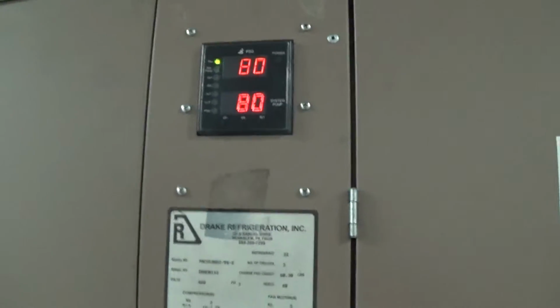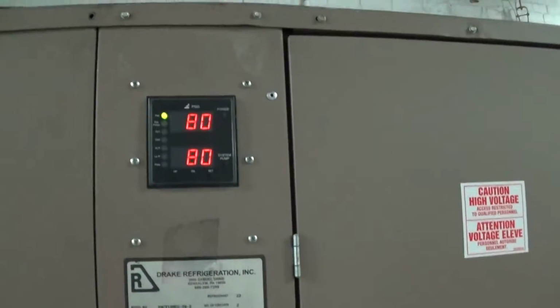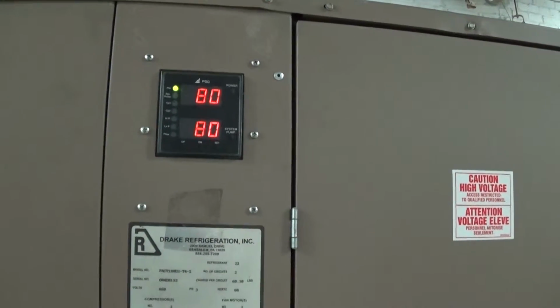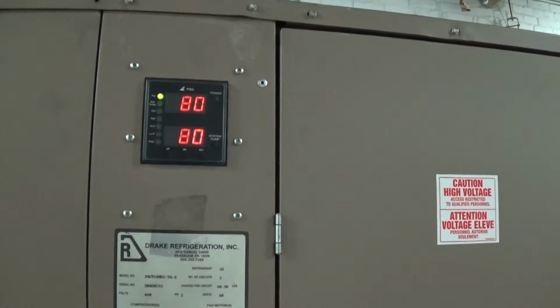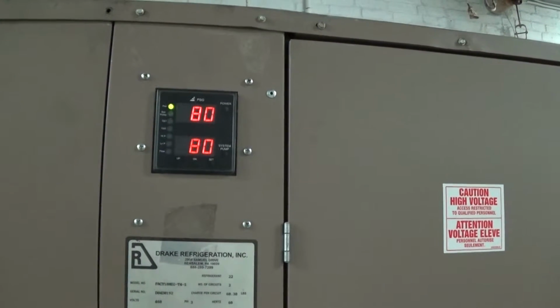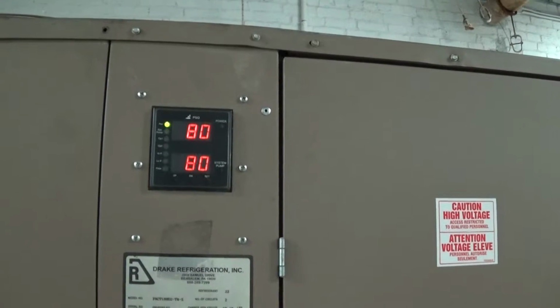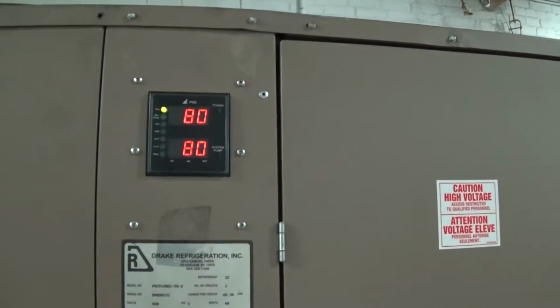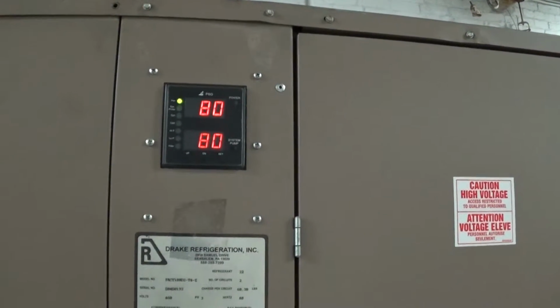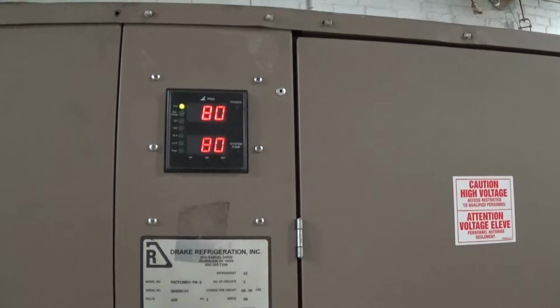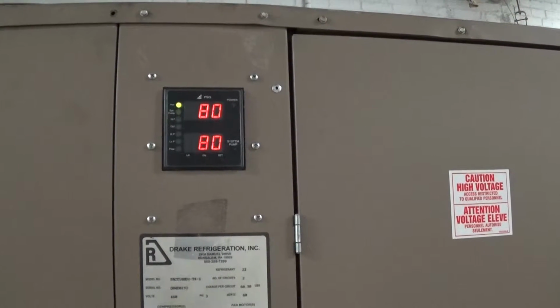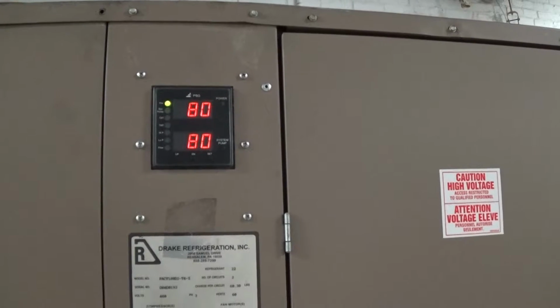So as soon as you power it up, the circulation or the evaporator pump does turn on, and it shows you 2 temperatures, the incoming and outgoing temperatures. In this case here, we don't really have a load on the unit other than the tank, so those are going to be pretty close to each other, with the exception of the little bit of a differential there.